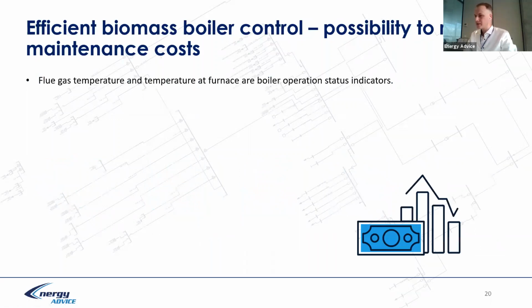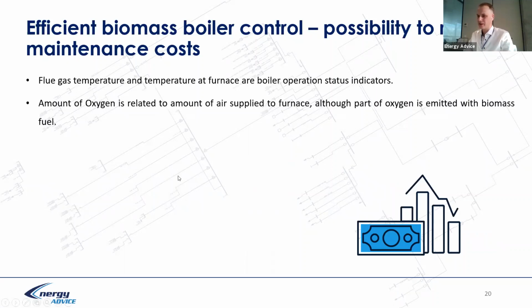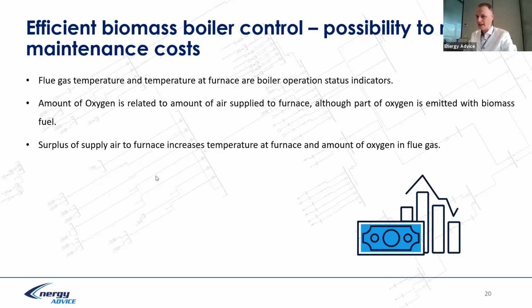Next, flue gas temperature and temperature at furnace boiler is operational status indicator. Amount of oxygen is related to amount of air supply to a furnace, although part of oxygen is emitted with biomass fuel. So don't make mistake on oxygen level and air supply level, because fuel consists of oxygen inside, and part of oxygen is coming from a fuel. Surplus supply air to furnace increases temperature at furnace and amount of oxygen in flue gas. It's general, so fuel surplus reduce boiler efficiency in general.